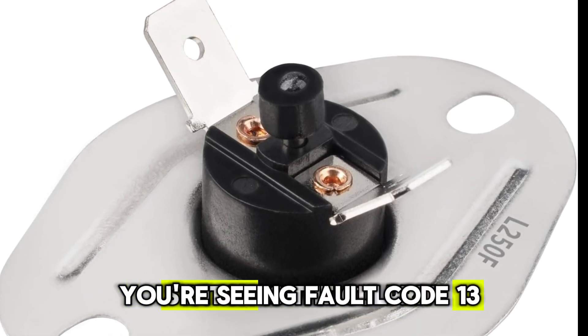So how do you know you might need to replace your furnace's flame rollout limit switch? If your furnace keeps shutting down with code 13 or 33 after you've already checked your air filter, blower motor, and vents, chances are the rollout switch is the culprit. They wear out over time, but it's a pretty inexpensive fix — you don't need a full furnace replacement, just swap this part.